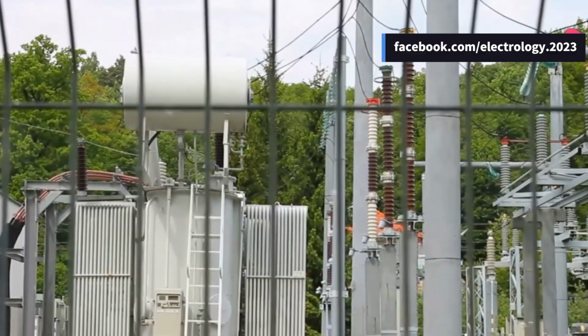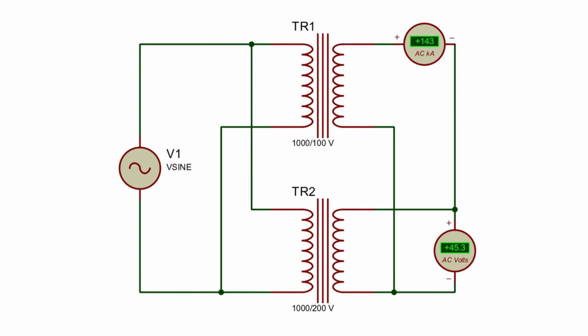First up, the voltage ratio. Simply put, if two transformers with different voltage ratios are connected in parallel to the same primary supply voltage, their secondary voltages will differ. If these secondaries are connected to the same bus, a circulating current will flow between them and consequently between the primaries. Since transformers have a small internal impedance, even a slight voltage difference can cause a high circulating current, leading to unnecessary extra I²R loss.